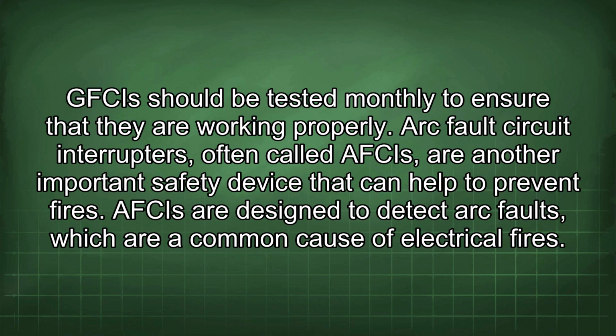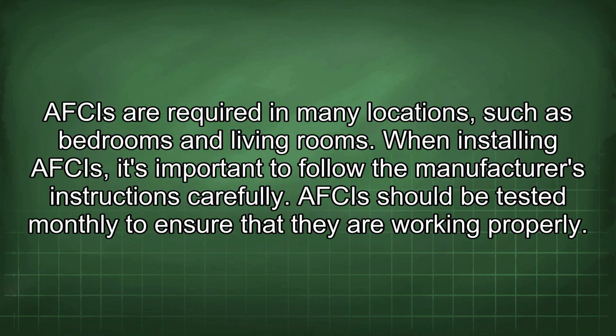Arc fault circuit interrupters, often called AFCIs, are another important safety device that can help to prevent fires. AFCIs are designed to detect arc faults, which are a common cause of electrical fires. AFCIs are required in many locations, such as bedrooms and living rooms. When installing AFCIs, it's important to follow the manufacturer's instructions carefully. AFCIs should be tested monthly to ensure that they are working properly.